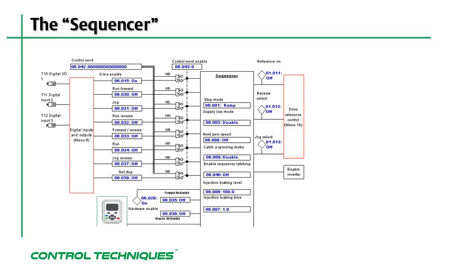It's important to understand how the sequencer is configured before wiring the drive. The sequencer configuration will determine which sequencer functions are assigned to which digital inputs on the drive. The sequencer configuration will change depending upon how the drive is configured. The drive configuration parameter is located in menu 0, parameter number 5.